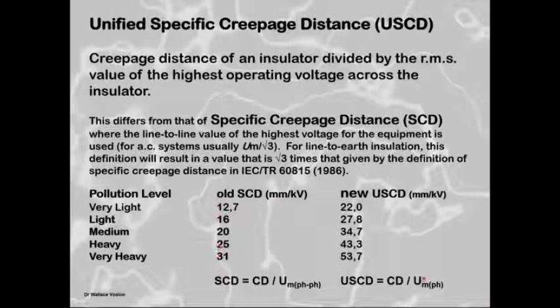Nowadays, that same value equates to a unified specific creepage distance where you use U max phase. So 31 millimeters per kV, making use of the old specific creepage distance definition, is 31. Now with the new unified specific creepage distance definition, it's 53,7. So you must be very careful when you specify in your specs. My suggestion is rather just specify the creepage distance and say it's so many millimeters, instead of what specific creepage or unified specific creepage distance you want, because that could be confusing in your selection these days.